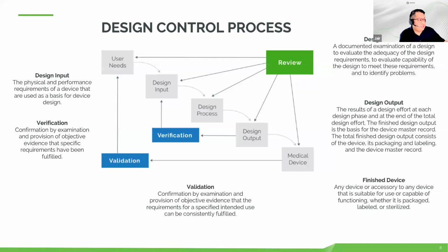So everything starts from us developing a design input based on our user needs, breaking it down through our design process, design output, verifying that design output to then deliver that medical device. And in between all that, we need to be able to review it. And that is one of the things that a lot of times it's the drawback. How is it that all the people that are involved are reviewing these processes?